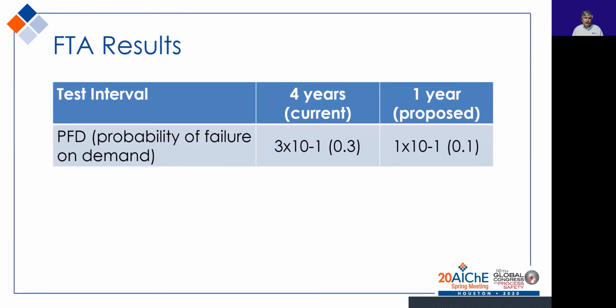The results of the fault tree: if we have a 4-year proof test interval, the probability of failure on demand is 0.3. If we have a 1-year proof test interval, the probability of failure on demand is 0.1. That is, 1 time out of 10, the gensets cannot provide the needed power during the main power outage. This probability of failure on demand is similar to a SIL-1 safety instrumented function, or SIF. We have to add this probability of failure on demand to the probability of failure on demand for the IPLs.